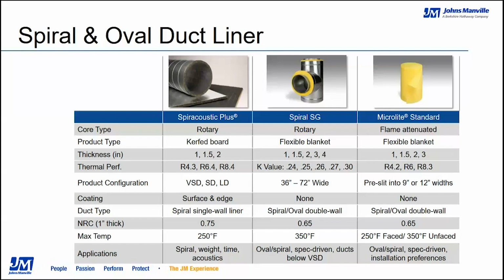The second product is our Spiral SG, which is our double wall duct insulation. The insulation is the yellow material, and double wall duct means you have an inner metal core, which can be solid or perforated, that's wrapped with a fiberglass blanket - the Spiral SG - and then that's inserted inside an outer metal shell. So double wall means two layers of metal with a fiberglass blanket sandwiched in between. We make several different thicknesses and widths of Spiral SG. It's a great application for double wall spiral or double wall flat oval duct, has been around a long time, can get to some small diameters, and is a tried and true method that lots of fabricators use for double wall spiral duct.